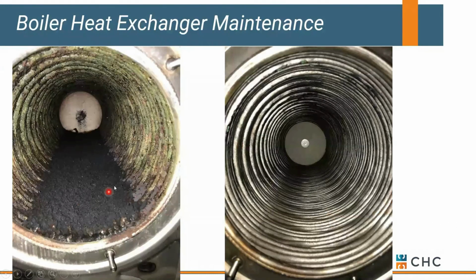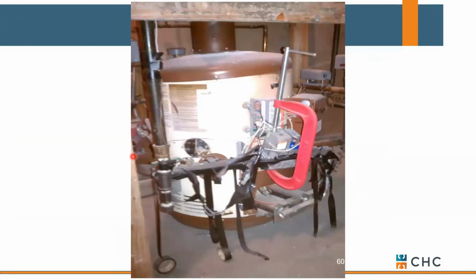Another good example of that, here's how it looks after 5 years of service, and here's how it looks after it was cleaned, okay? Typically, you're into a boiler every 9 to 12 months for annual maintenance. So it should be something that you add to your list when you're considering a boiler choice. Now, unfortunately, the American mindset is let's buy a new product, let's stick it in a closet, and we'll come back in 5 to 10 years and check on it. You can't get away with that these days if you're going high efficient.